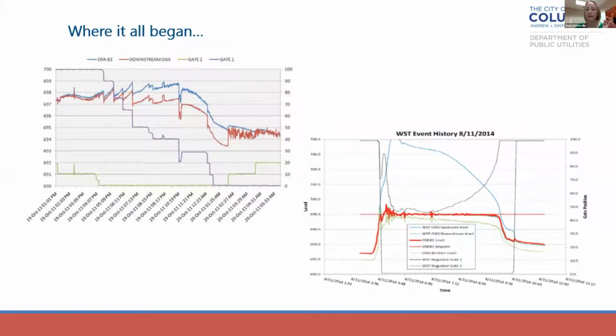These two graphs are at our largest CSO, which we call DSR 83. It requires careful management of our sewer levels and our regulator gates at a nearby structure to control what's going on with the CSO. Typically we would manually operate gates, closing them to decrease downstream sewer levels in steps during wet weather events. This manual operation would result in overcorrection, restricting flow in the downstream sewer unnecessarily, and it wasn't the greatest way to operate this facility. So we put in automatic logic and controls on these regulator gates to allow for more frequent control and adjustment to maximize conveyance and treatment.